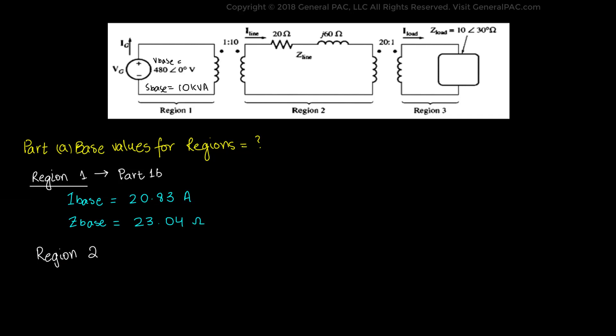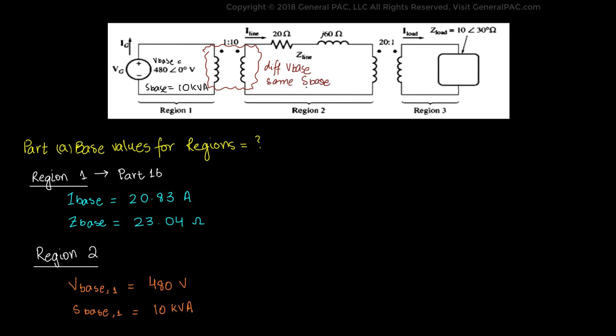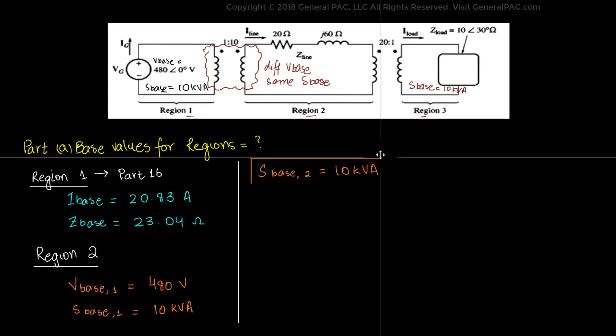Region 2. First, let's write down the base values given for Region 2. We know the rating of the generator — both V-base and S-base — for Region 1. Since there is a step-up transformer between Region 1 and Region 2, the V-base for Region 2 will be different; however, the S-base will remain the same. In fact, the S-base remains the same for Region 1, Region 2, and Region 3. So the S-base for Region 2 is simply equal to 10kVA.